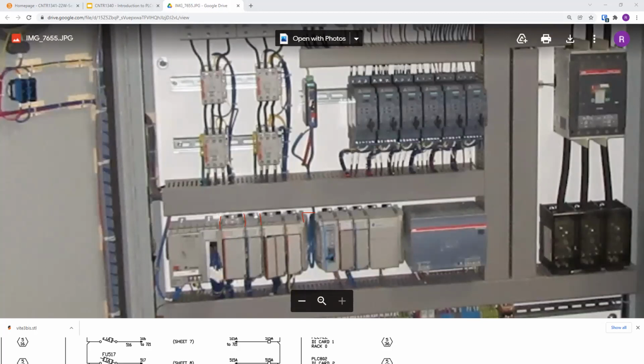I'm not going to say for certain what that is, but you can get these end caps. This end cap would report back to the processor. It's the end of this particular module. And then here, you could skip over to another rack, and they will do some interconnection. That'll be a power supply to power these 3 cards, or it looks like it might be a remote IO. So even though I said earlier most things have racks, there are platforms that do not.